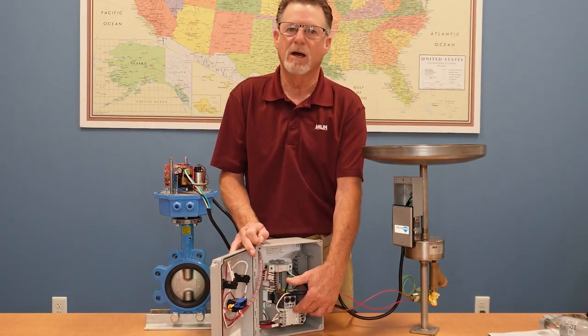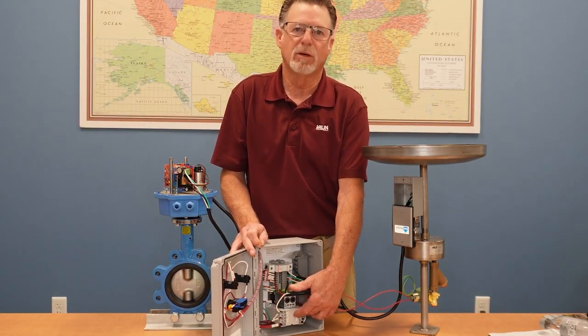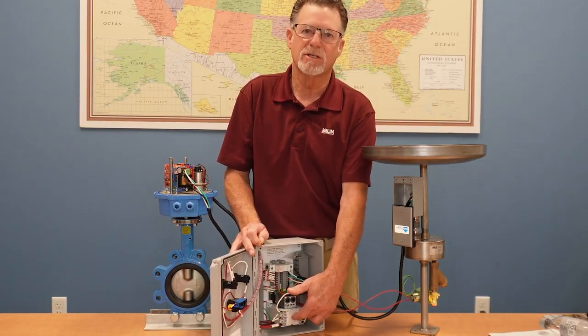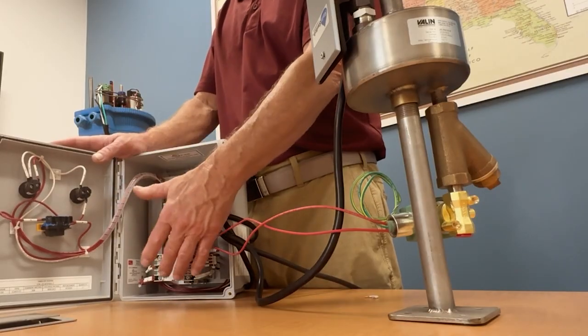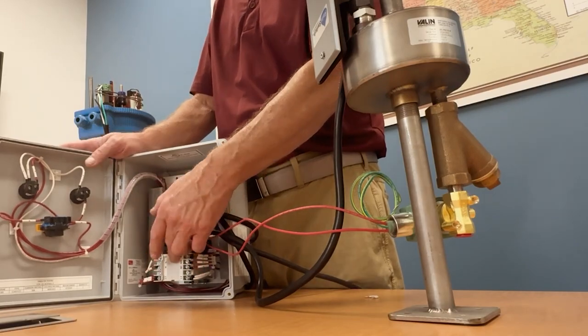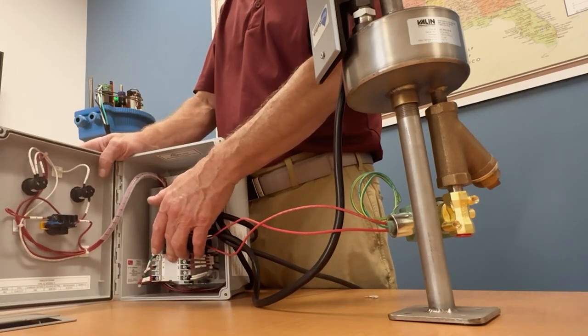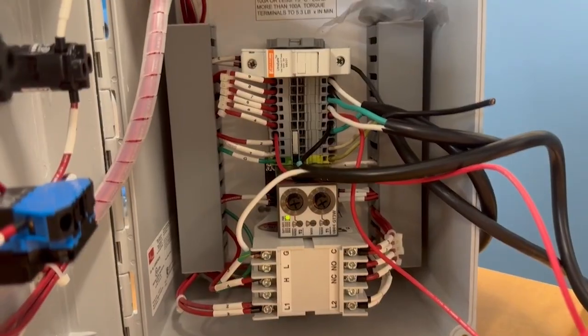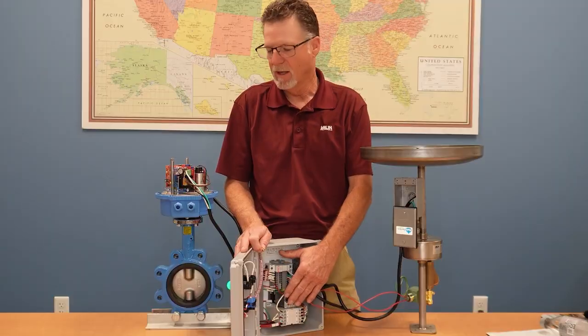You can't just go out and buy a single pole double throw relay and change this out. If you overload this and the relay fails, you have to replace it with this exact relay. Do not substitute something else. You must use this relay.